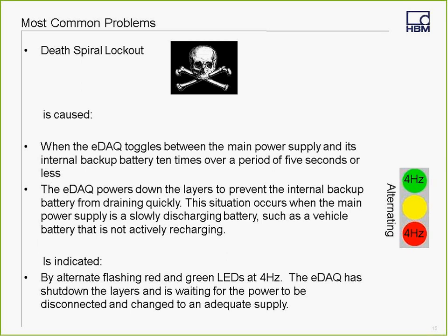Another common problem is a death spiral lockout. It's caused when the eDAQ toggles between the main power supply and its internal backup battery 10 times over a period of 5 seconds or less. The eDAQ powers down the layer to prevent the internal backup battery from draining quickly.